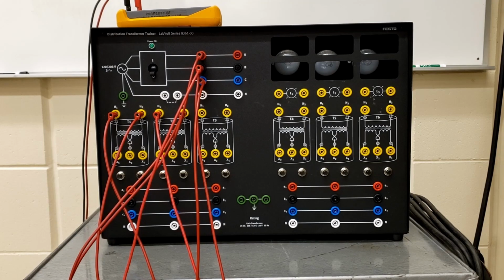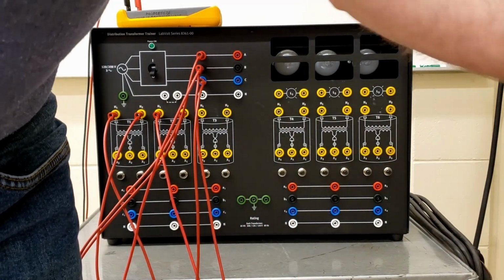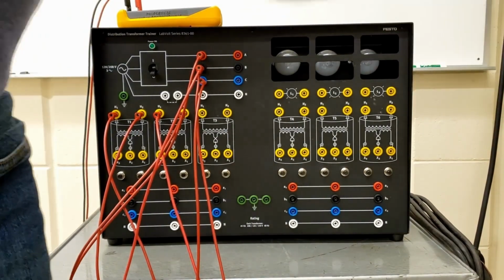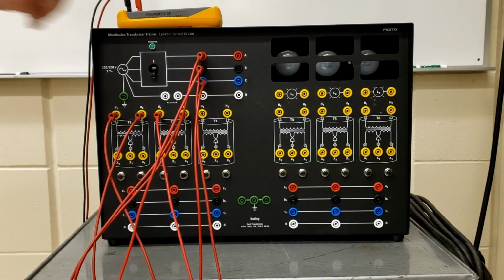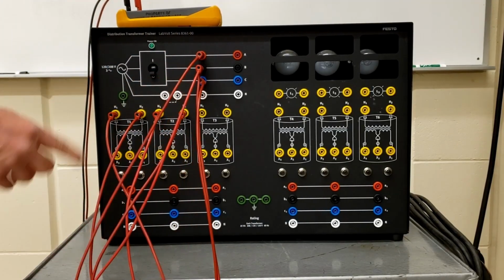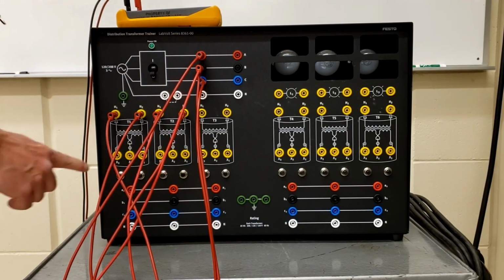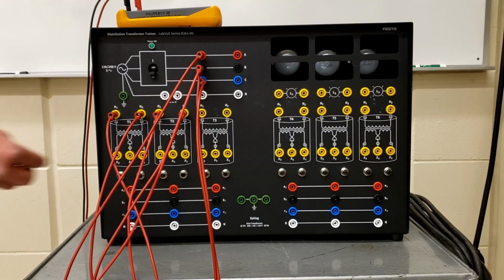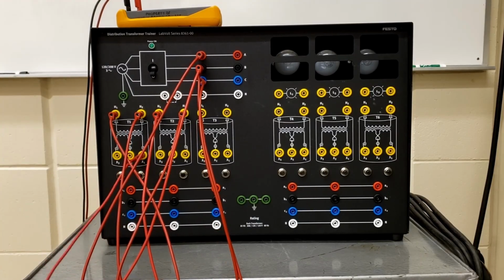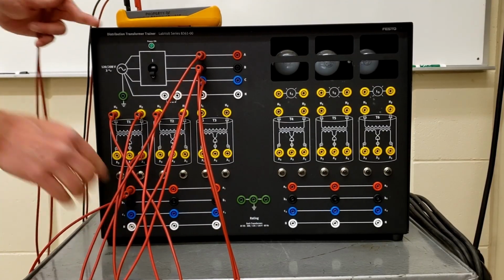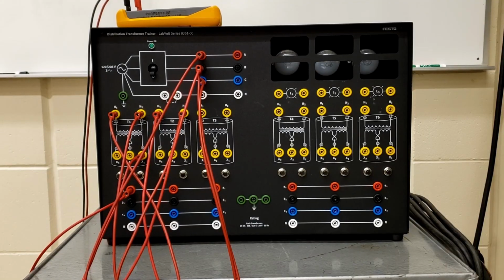Okay, let's take a look at the secondary now. So we got X1 to A. Again, this one's a 0 degrees phase shift, so that means that if we're feeding H1 with the A phase, then X1 is then going to feed our A phase as an output. Remember that H1 and X1 are going to have the same relative polarity.